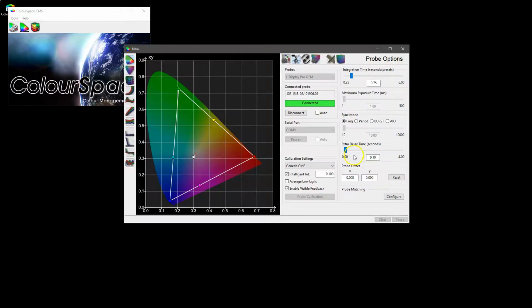The other use for extra delay time is if the display has colour memory. In other words, it takes a little while for a changing colour to settle. Some technologies like plasmas and OLED can suffer this. So you may want to add a little bit of extra delay time to allow the patch to settle before you start reading it. Again, the slider sets the value, or you can directly set any value you want using the numeric input.